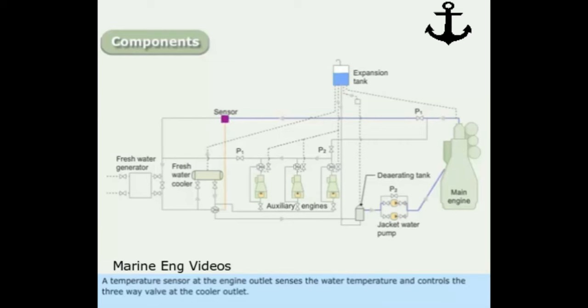A temperature sensor at the engine outlet senses the water temperature and controls the three-way valve at the cooler outlet. Depending on the temperature, water bypasses or flows through the cooler.